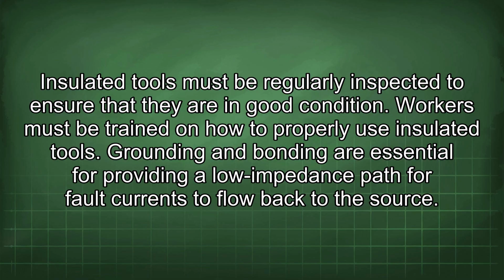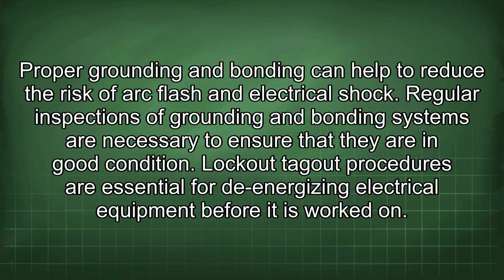Grounding and bonding are essential for providing a low impedance path for fault currents to flow back to the source. Proper grounding and bonding can help to reduce the risk of arc flash and electrical shock. Regular inspections of grounding and bonding systems are necessary to ensure that they are in good condition.